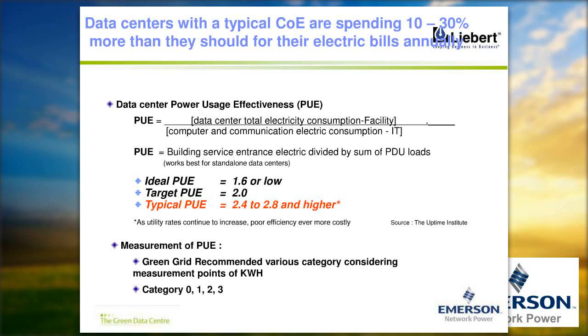So while category 0 specifies the instantaneous measurement of this ratio, categories 1, 2 and 3 mention that it has to be on annualized kilowatt hour, measured at facility level and measured at IT level, computing level. And categories 1, 2, 3 are differentiated based on where you are monitoring that kWh. It could be at UPS output, at PDU output, or at rack input or server input. So this is how the categories of PUE are described, and based on which the PUE measurement happens.